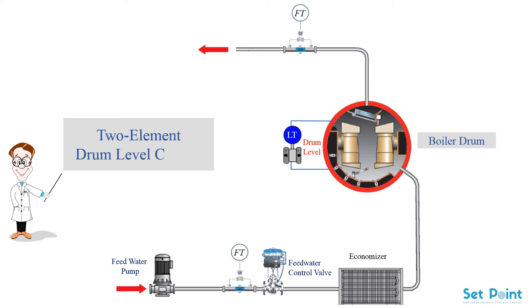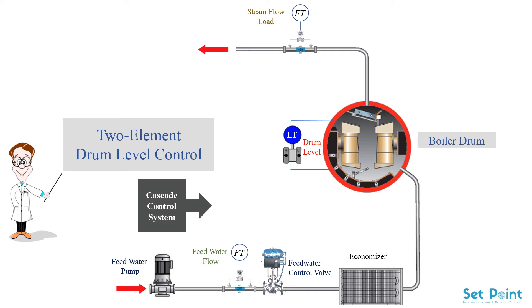Two element drum level control. In this mechanism, one more variable is controlled in the process apart from the level. That variable is the flow rate — the flow rate could be of feed water or the steam, any one of them. They form a cascade control system with the level controller being in the primary loop, and the input from it is used to set the second loop which consists of a flow rate controller. The accuracy is much better and also faster than single element control.